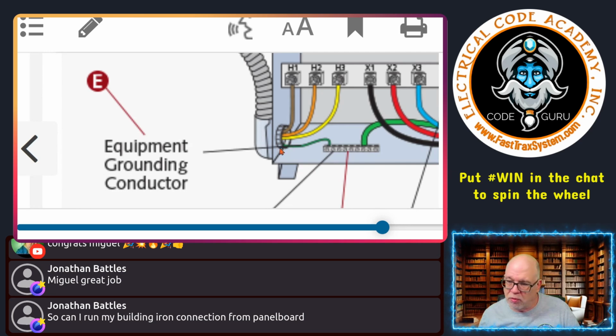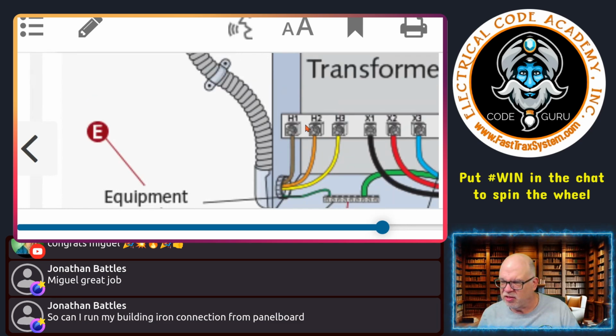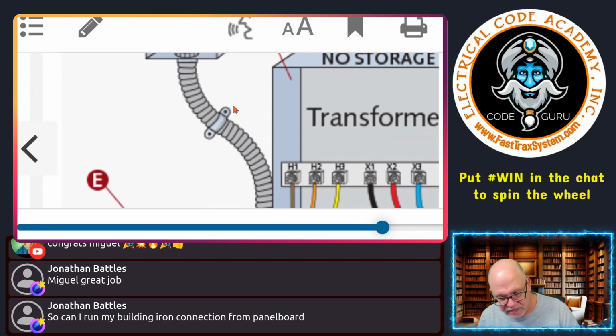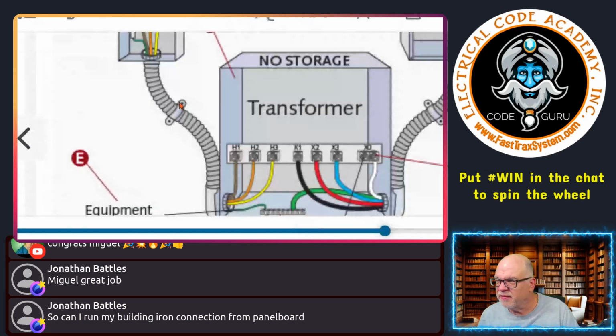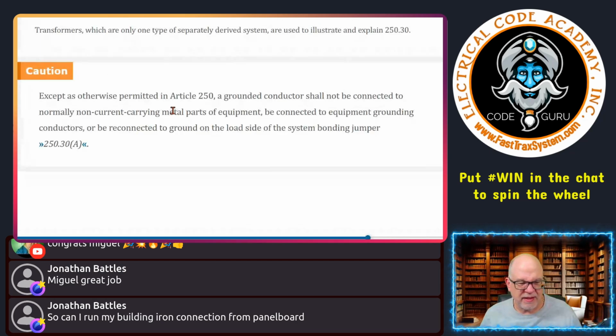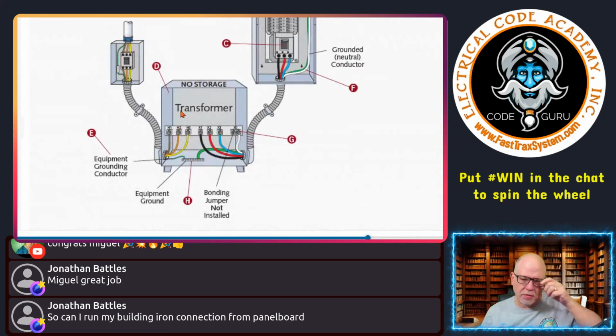You notice there's no loop here. There's no running it through a lay-in lug. This is a pure punched out KO. Everything's fine in this type of scenario. But you did have to run an equipment grounding conductor through there because it still has to clear an overcurrent protective device on the primary side. Okay, so let's see here. Now, if I can get this to go back to normal size. Okay, back to normal size. There we go.